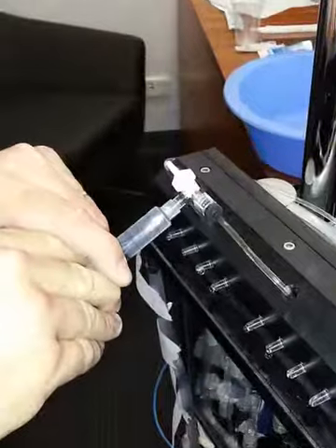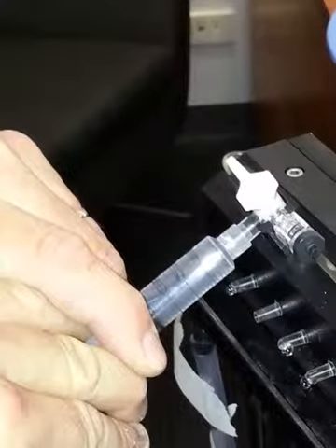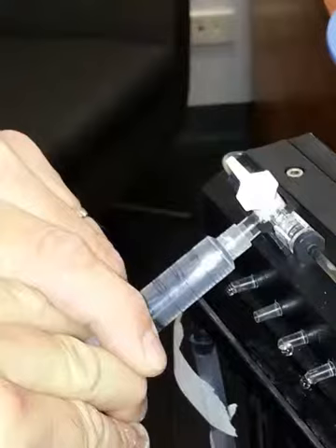Remember that the water will be under pressure, so you will need to control the movement of the plunger of the syringe. Now turn the lever back to the left and firmly press on the syringe plunger, pressurizing the manifold. You may need to use 2 hands to generate a sufficiently high pressure. Ensure that the syringe does not slip off or you will get a stream of water across the room.